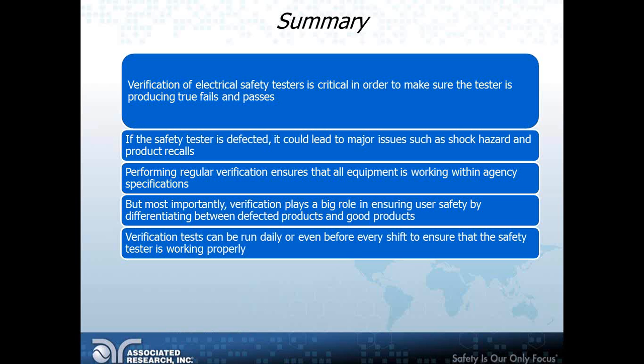in a leakage tester. The verification method that we went over for line leakage test was a very basic verification to see if the leakage measurement is being done correctly, which this test that we went over should verify that much for you. But once again, you can go into a lot more detail and design or come up with your own verification processes.